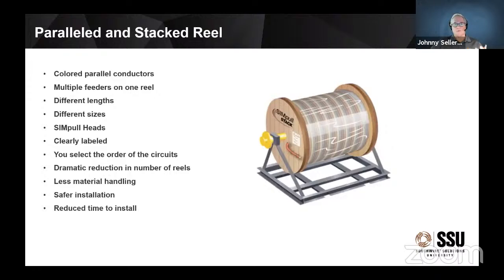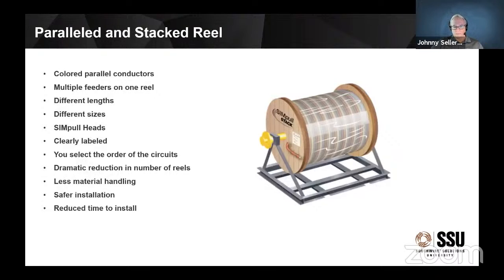We're going to use colored parallel conductors and parallel them on a reel. Stacking means we're going to put multiple feeders on one reel. They can be different lengths, different sizes. We're going to put SIMpull pulling heads on them and they'll be clearly labeled. You decide the order you want to pull these circuits off that reel. It dramatically reduces the number of reels, meaning less material handling, less reels to move around, much safer, tremendously less time to install, and you're increasing your profits.